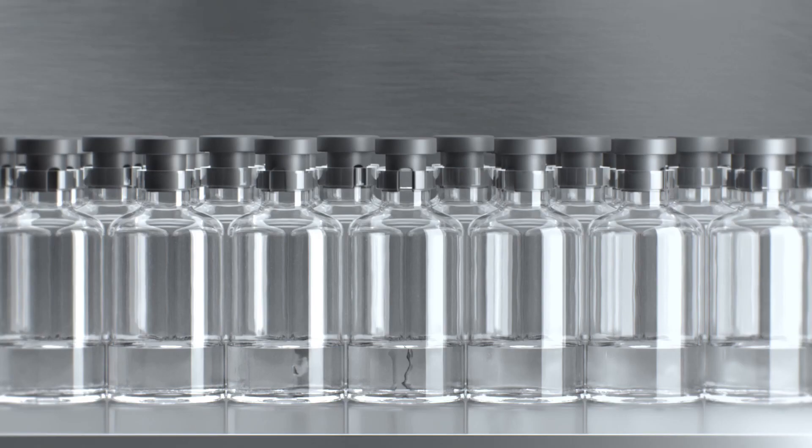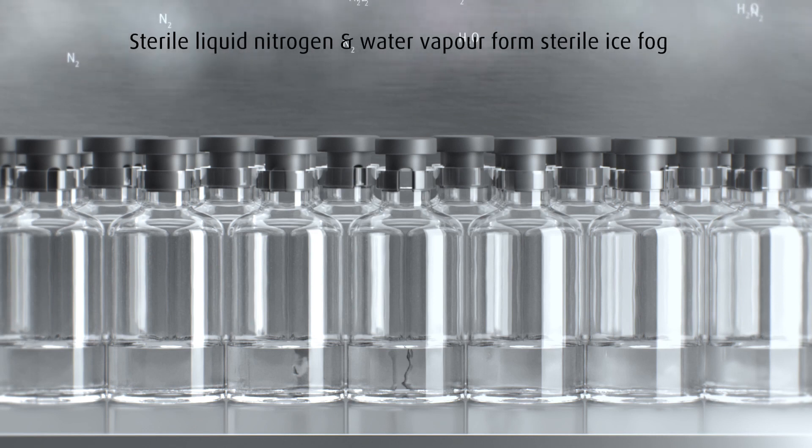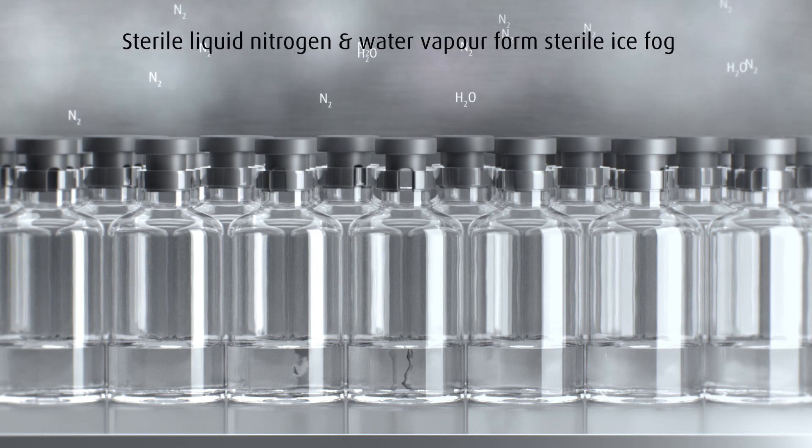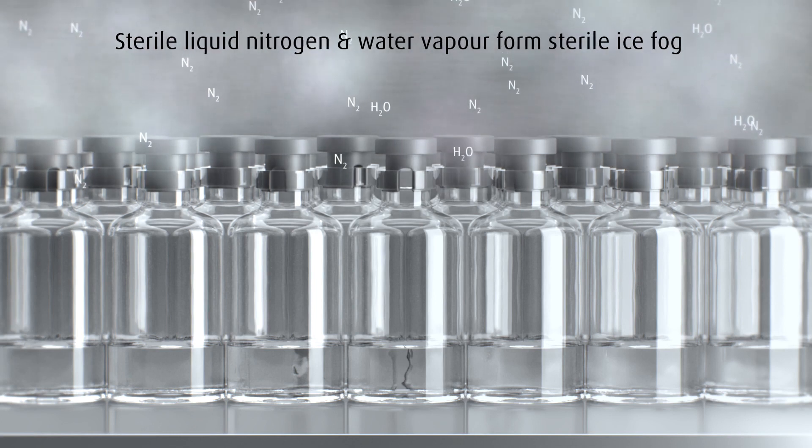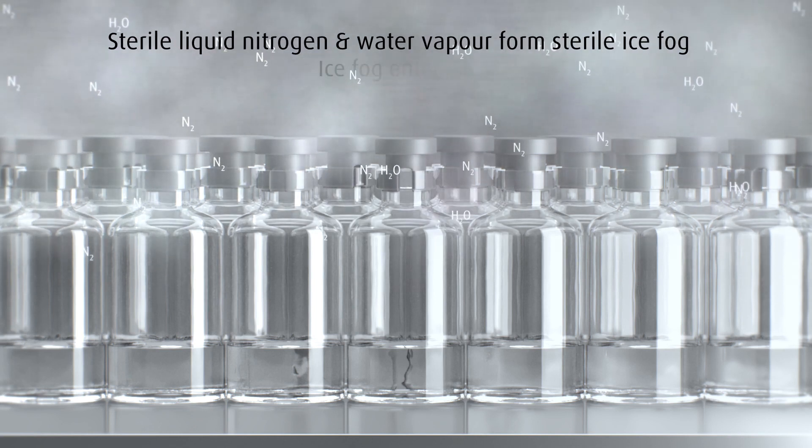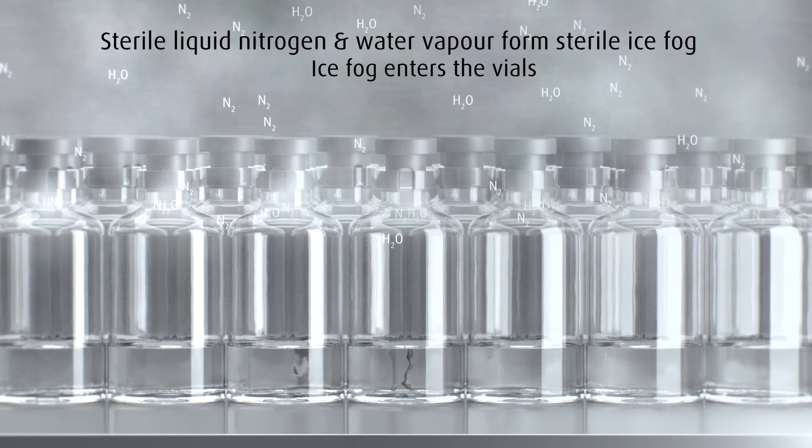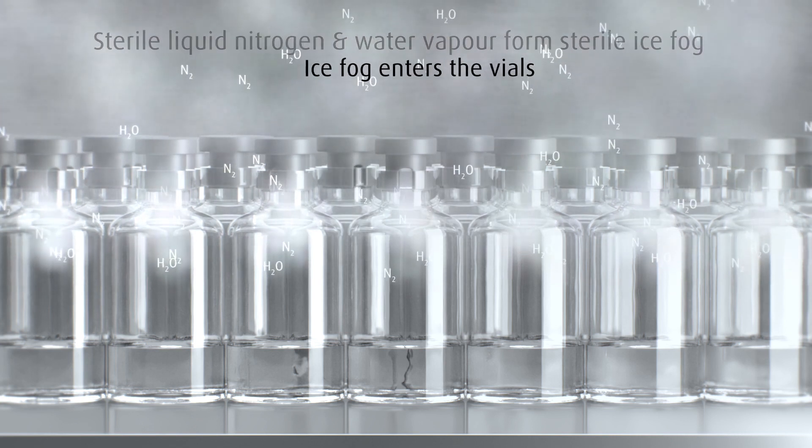A combination of sterile liquid nitrogen and water vapor form a sterile ice fog which is introduced under defined conditions. It uniformly fills the chamber and enters the vials containing the supercooled liquid pharmaceutical solution.